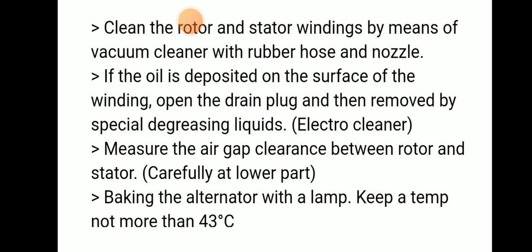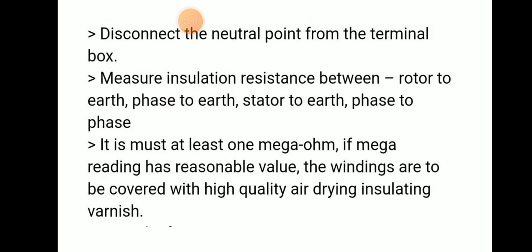And we have to bake the alternator with a lamp. That means we have to maintain a temperature of not more than 43 degrees Celsius. So it should not be too cold and it should not be too hot. Because here the machine is turned off and not running, the temperature should not be too low or too high. And disconnect the neutral point from the terminal box.